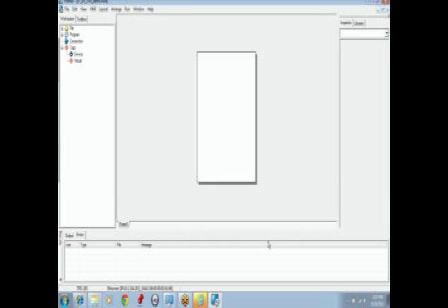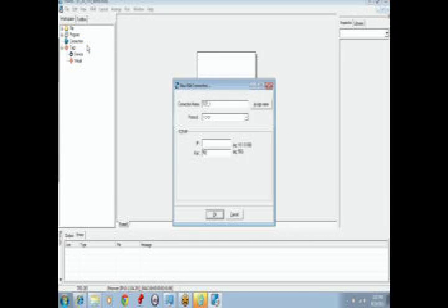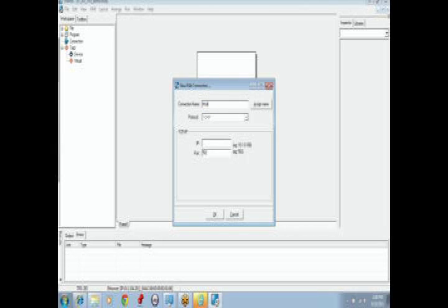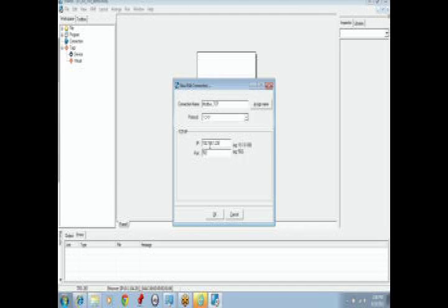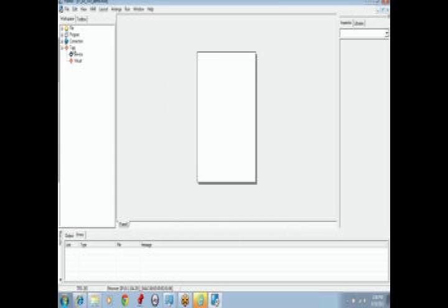We will select Ladder Logic for this example. To set up the Modbus device, we will right-click on the Connection button and select New Connection. We will select a name for this connection, Modbus TCP. We will input the IP address for the connection and the port. The default for Modbus is port 502. Click OK.